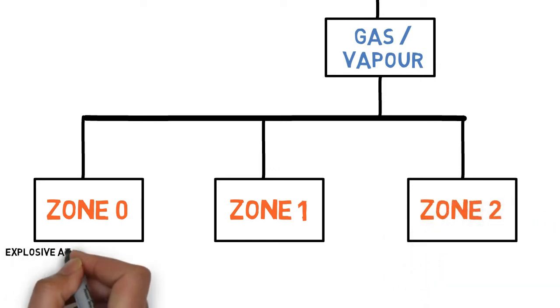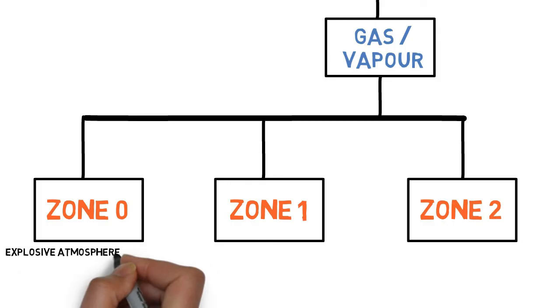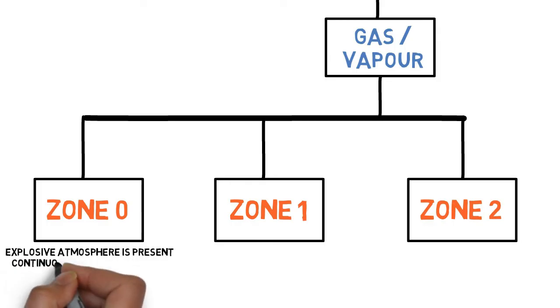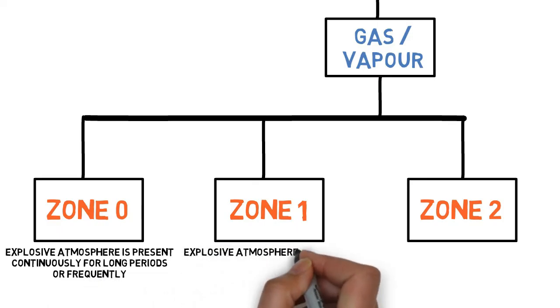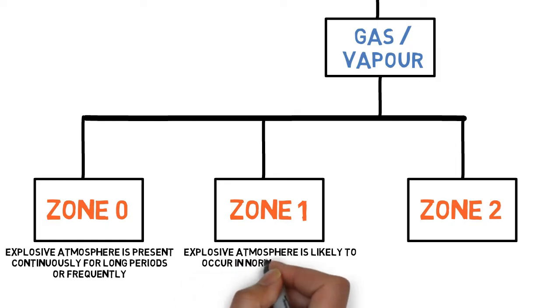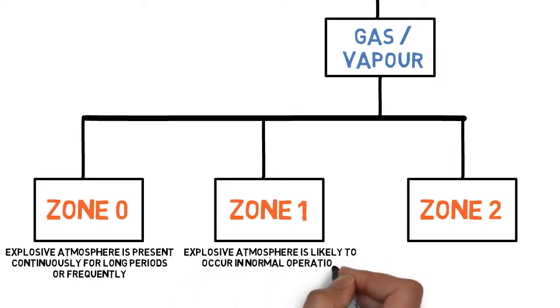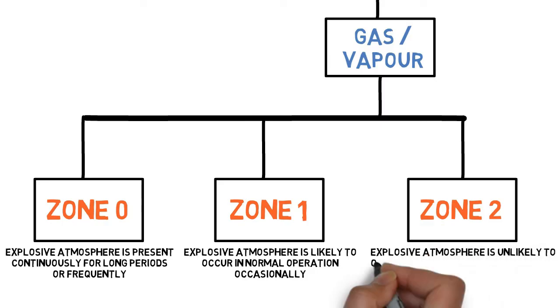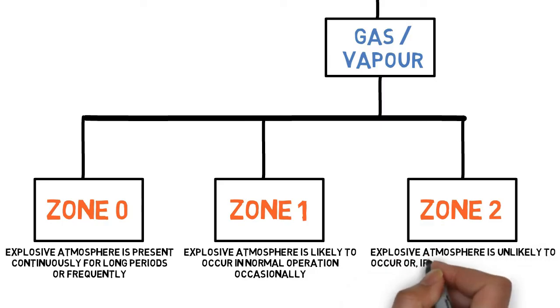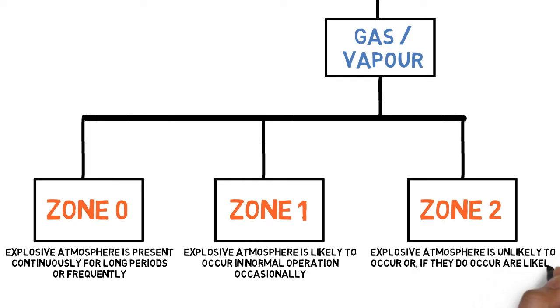In Zone 0, Explosive Atmosphere is present continuously for long periods, or frequently. In Zone 1, Explosive Atmosphere is likely to occur in normal operation occasionally. In Zone 2, Explosive Atmosphere is unlikely to occur, or if they do occur, are likely to do so for a short period only.